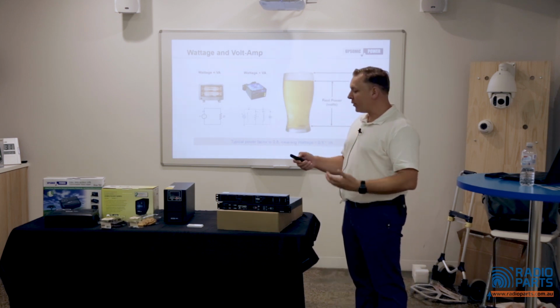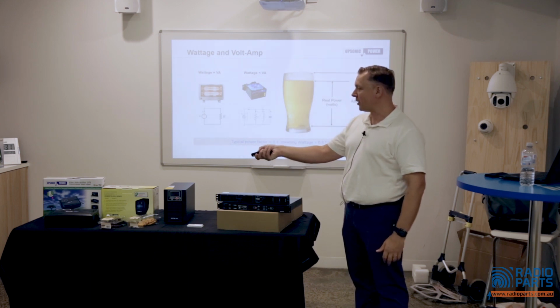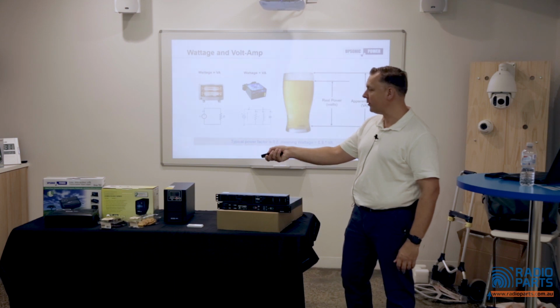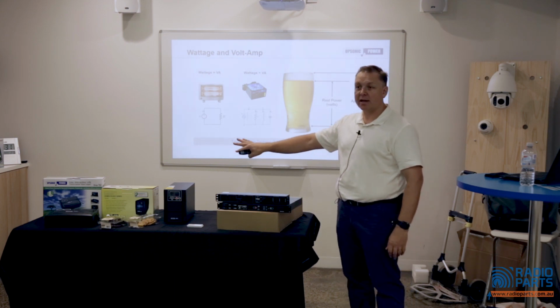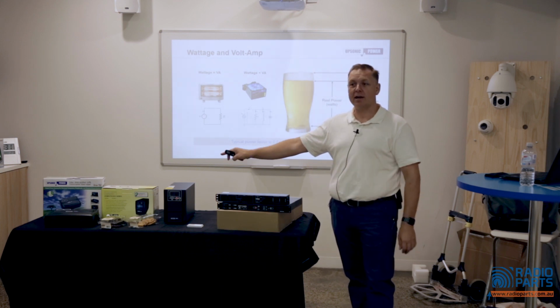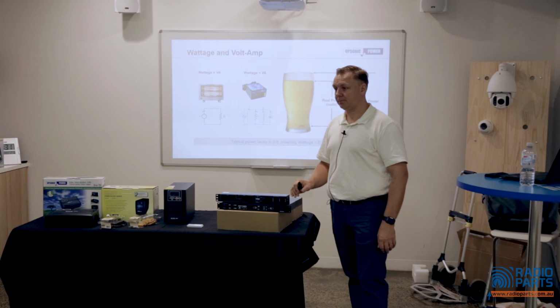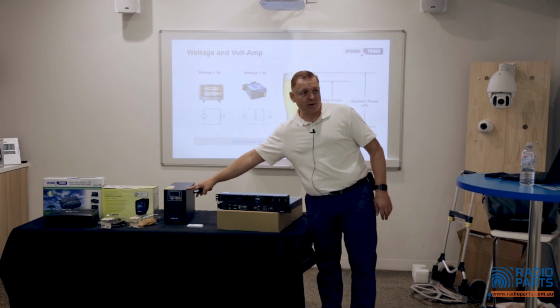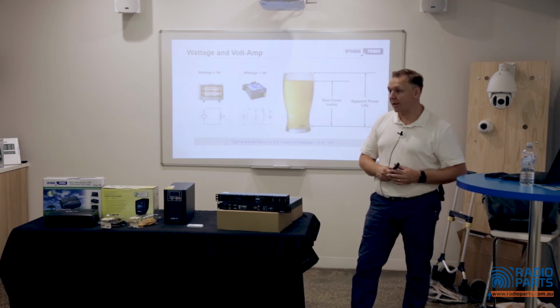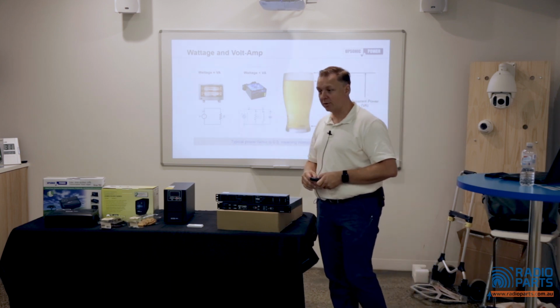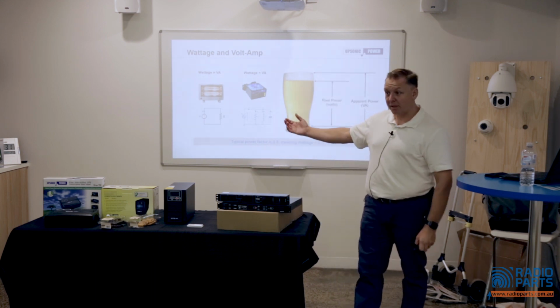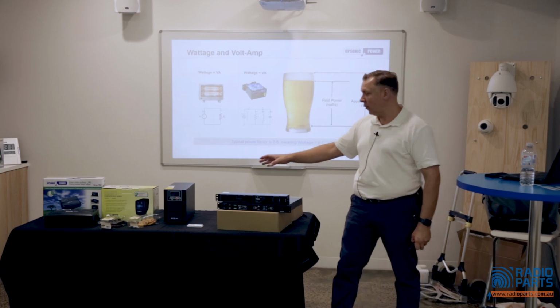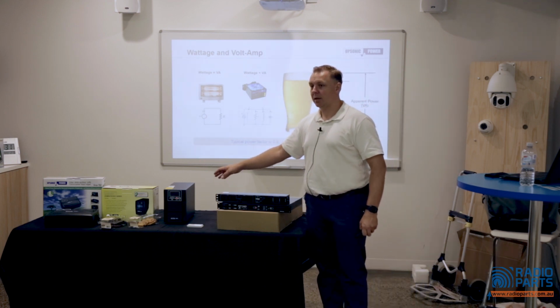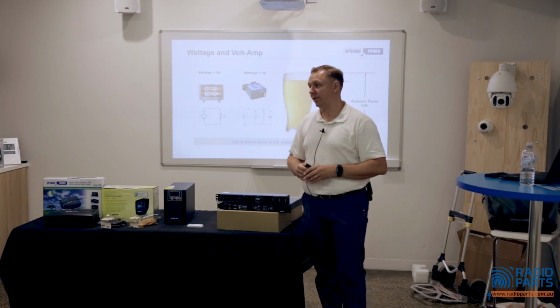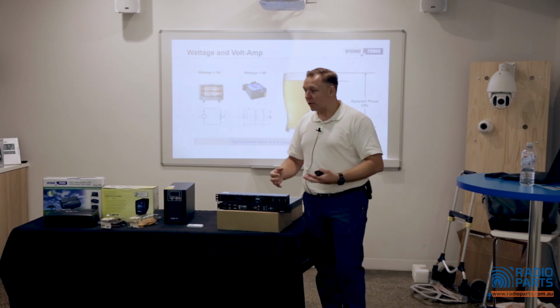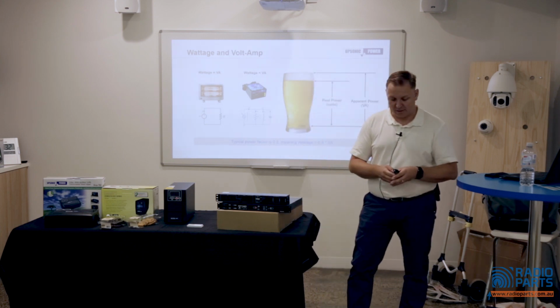So the important consideration is when we talk about smaller UPSs, our standby systems, and we'll get into the detail of that in a minute. Typically, they're a 0.7 power factor unit. So if you've got a 1 kVA UPS, you're going to get 700 watts out of it. When we go to our dual conversion systems, like you said, they're 0.7 power factor. Yeah. Okay. So you're getting 700 watts from a 1 kVA unit. When we go to the bigger ones and our big hardwired systems, typically we're at 0.9. So a 1 kVA UPS will get 900 watts. And one of our other models sits in between, which we'll cover in a second. So that's a really important consideration for you when you're sizing the right thing for your customer.